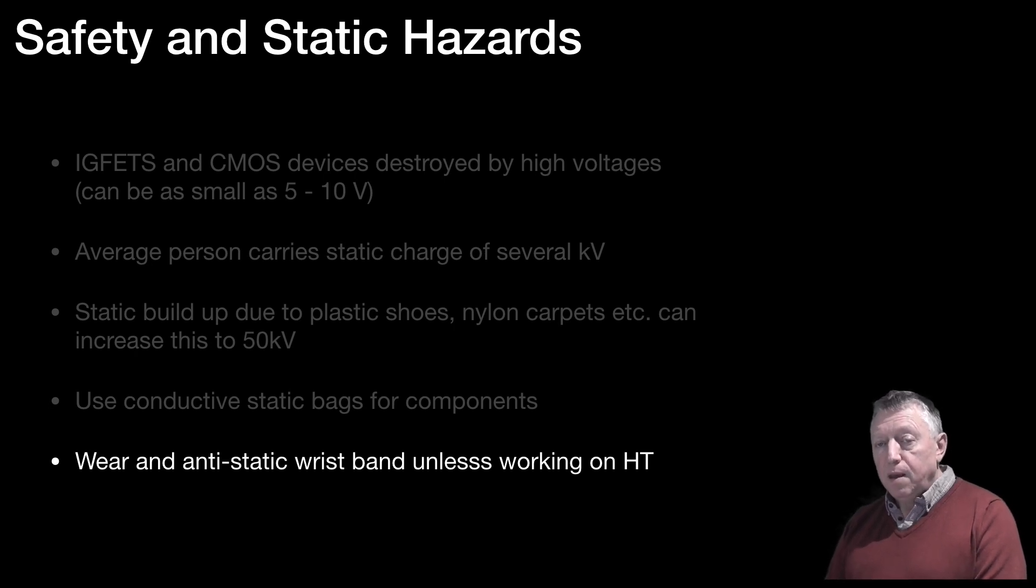And then the final point here is wear the anti-static wristband, unless working on HT. Now, an anti-static wristband is a band that goes around the wrist and connects to earth. And it connects to earth via a high-value resistor built into the band itself. So, this provides a degree of safety, but if you're working on high tension, in other words, very high voltages, it isn't a good idea to wear a static band because that increases, for example, risk of electric shock across the heart.